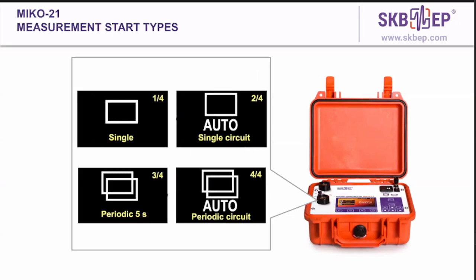There are 4 methods programmed in the instrument for resistance measurement startup. Mode 1, single shot startup, that is startup by pressing the start button located on the front panel of the instrument. Mode 2, startup against circuit closing, automatic measurement startup against the test circuit closing. Mode 3, periodic startup. Measurements are started at pre-specified time intervals of up to 20 seconds. And the last but not least, mode 4, periodic circuit, regular automatic measurement startup against the test circuit closing.